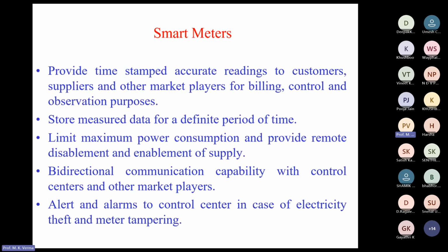Now, what are smart meters? Smart meters provide time-stamped measurements, because that is the advantage of synchrophasor technology. Unless all measurements are performed at almost the same time, they will be of no use, because the voltage and current keep on changing. So if you perform a measurement at some location at some time, and there is a time delay in the measurement at another location, you cannot combine these two to do computation, because the system is highly dynamic. So voltage and current all keep on changing. So we need time-stamped measurements, which are provided by the smart metering schemes.